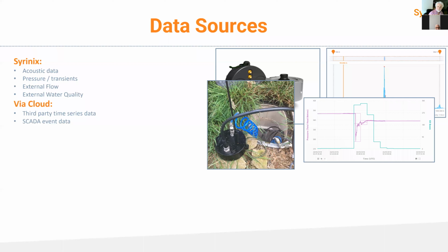These run 128 samples a second, 24/7, looking at pressure, and we report the minimum, mean and max pressure for every minute of the day. We also have an algorithm looking for pressure transients and water hammer. If we see a water hammer event, we section up the data and send it straight away for analysis to our cloud platform, Radar. This pressure transient functionality is in both the acoustic product and the pressure-only product.